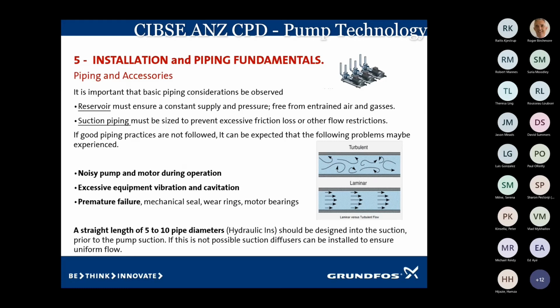And if we're looking at trying to save energy, the best way to do it is to make sure whatever we're putting in there can do its best. If the pump is struggling, if it's starving, it's not going to perform. It's going to be inefficient. So we need to make sure that the suction piping, and or the water supply coming to the pump, is correctly sized.